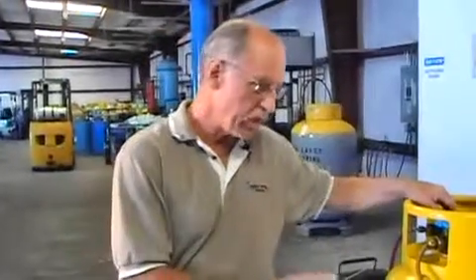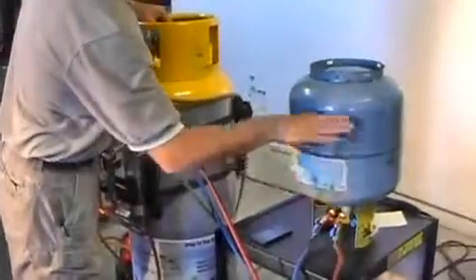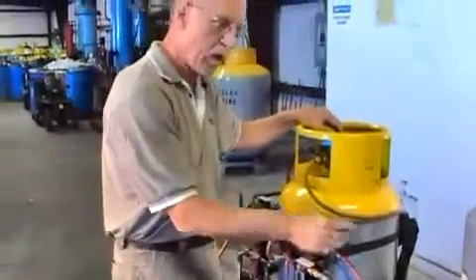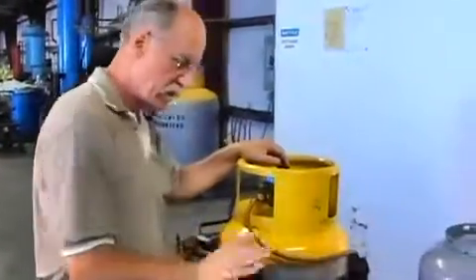As you can see we took about a minute, minute and a half and we transferred the 20 pounds of liquid that was in this tank. We warmed it up. We pushed that liquid out. A minute and a half the sight glass cleared up. I also hear the hissing in the tank which tells me the liquid is gone.